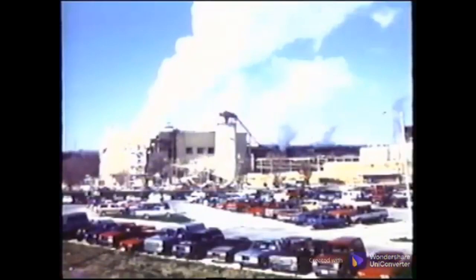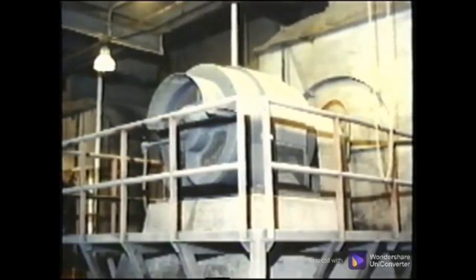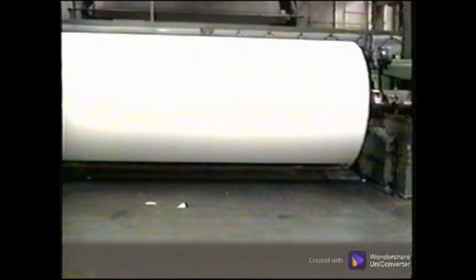Some manufacturing processes require specific and uniform temperatures in order to maintain high quality. Thermal imaging can provide the information needed to correct problems and increase quality production. This example shows the paper from a paper machine as it is being rolled up. It has just come from the dryer section, where it should have dried uniformly, yet there is definite streaking indicating a cold area. This area did not dry thoroughly, which points to a problem with the drying process.